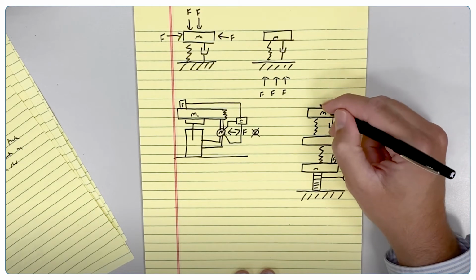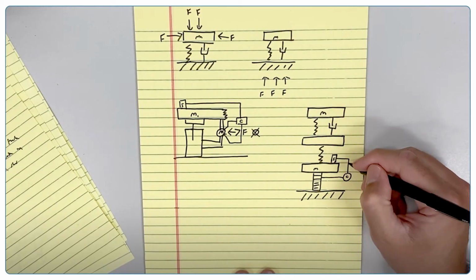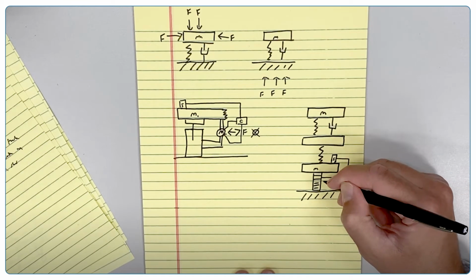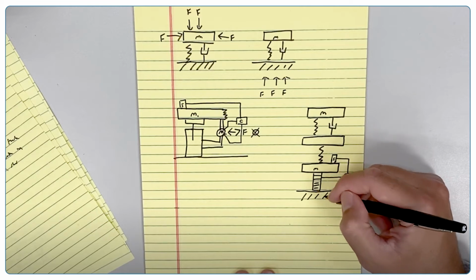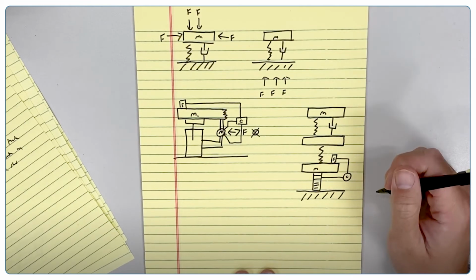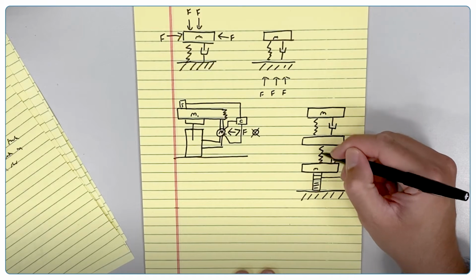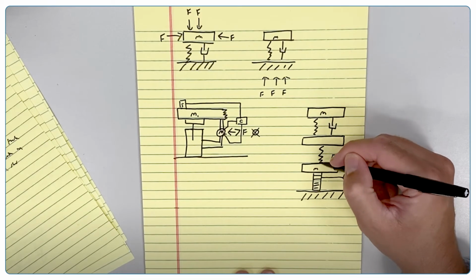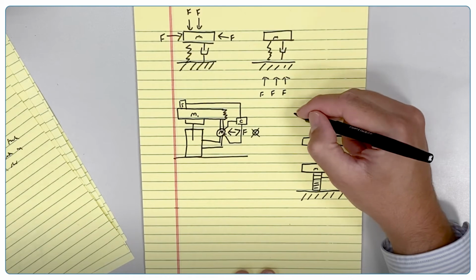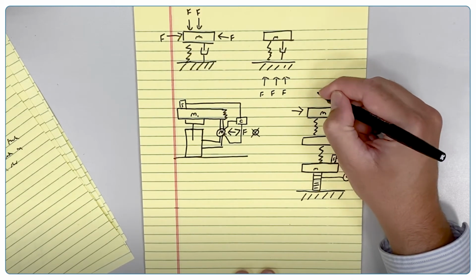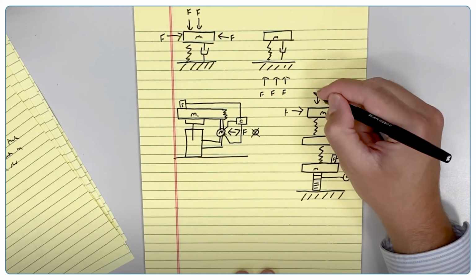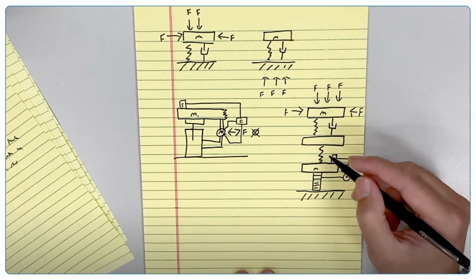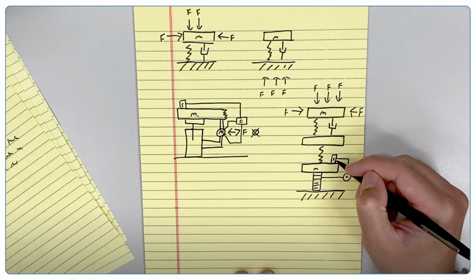Here, we have a system that is ideally suited for floor vibration, since the sensing feedback loop is completely isolated from any payload noise and frees up a good deal of control bandwidth to focus on low frequency cancellation and expand and contract the piezos to provide the proper displacement. This spring, at the second stage of the serial type system, provides that isolation. So if there is a good deal of payload motion, it's independent of the sensing feedback control system.